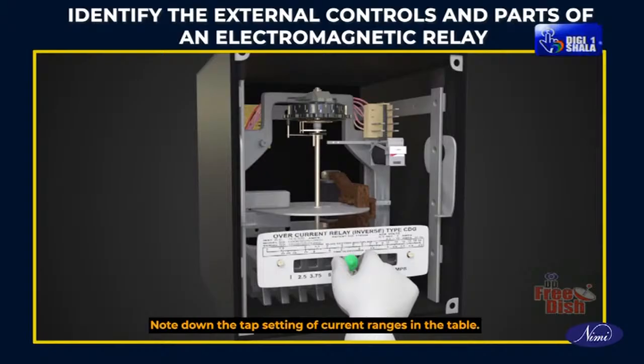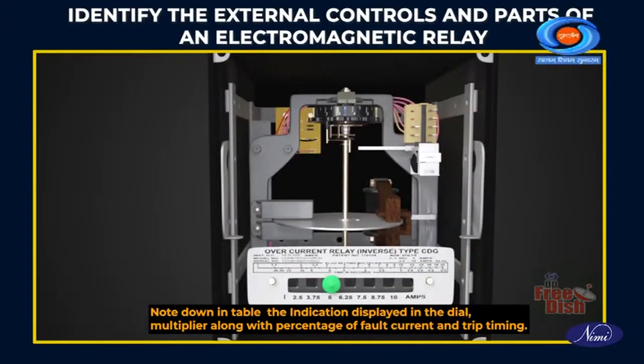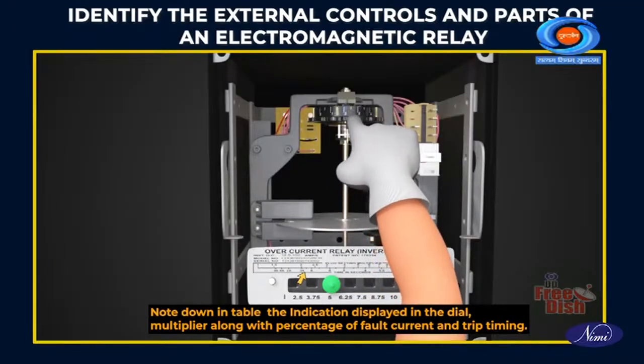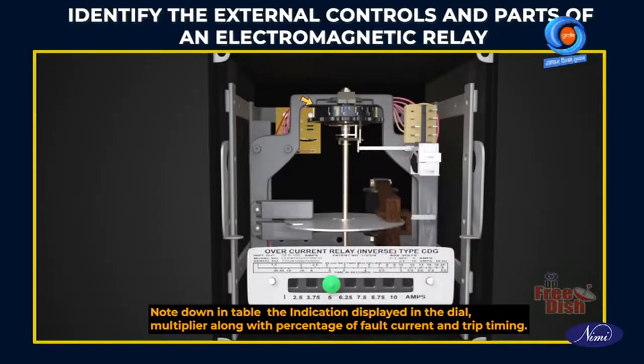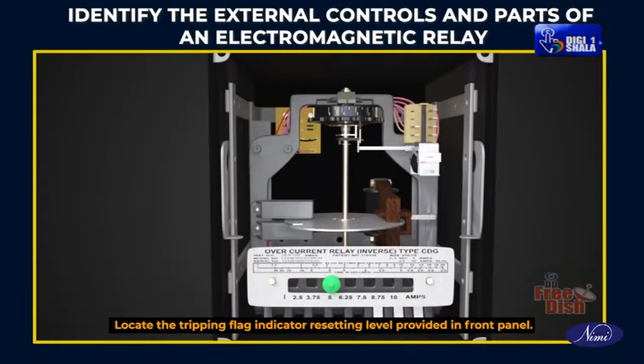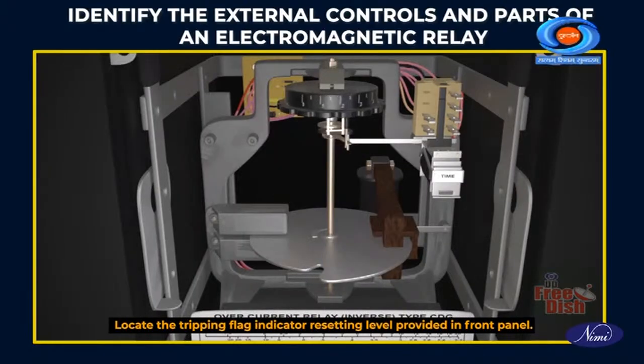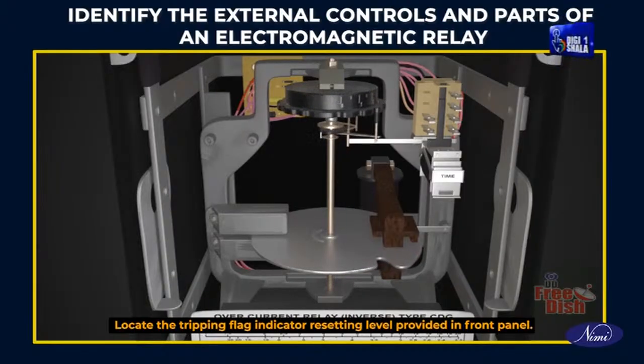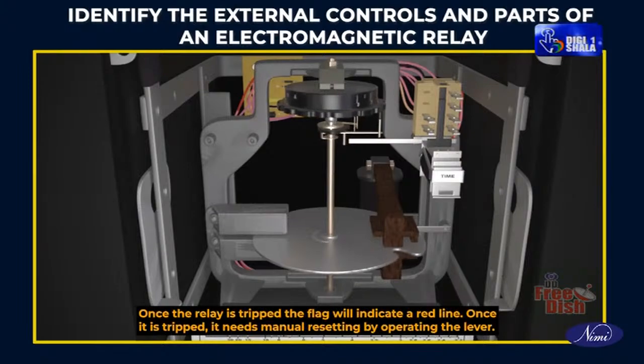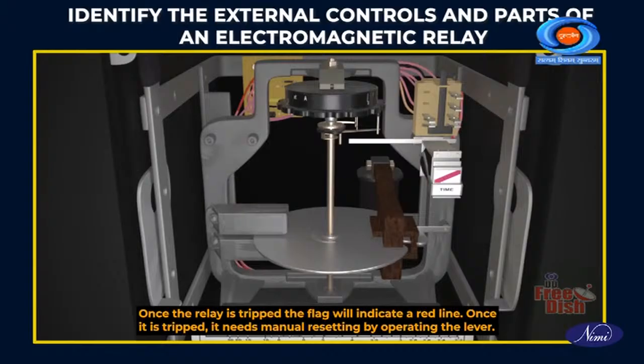Note down the tap setting of current ranges in the table. Note down in the table the indications displayed in the dial, multiplier along with percentage of fault current and trip timing. Locate the tripping flag indicator resetting lever provided in the front panel. Once the relay is tripped, the flag will indicate a red line. Once it is tripped, it needs manual resetting by operating the lever.